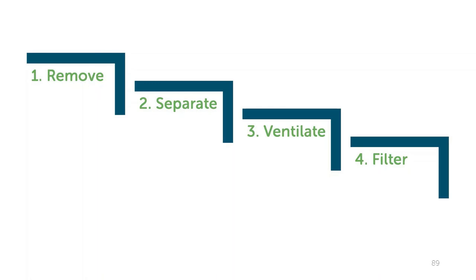There are 4 steps to improving indoor air quality: remove, separate, ventilate, and filter. Filter selection, ventilation design, and system installation greatly impact indoor air quality. A leaky home does not provide good indoor air quality. Balanced ventilation is better than exhaust only, and supplies need to go to rooms with doors that will be occupied for long periods of time, like bedrooms. You also need spot exhaust in kitchens.